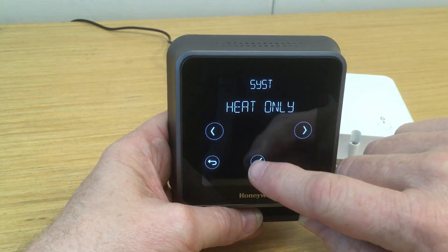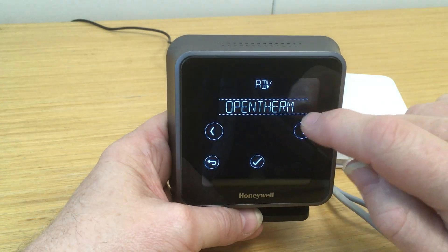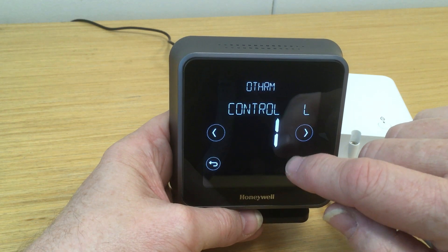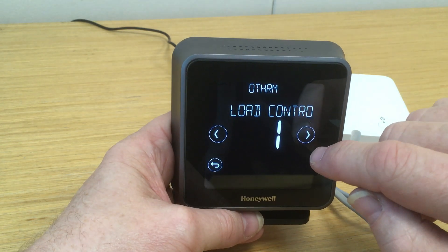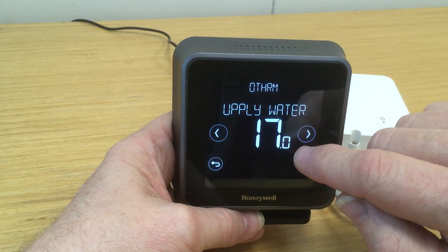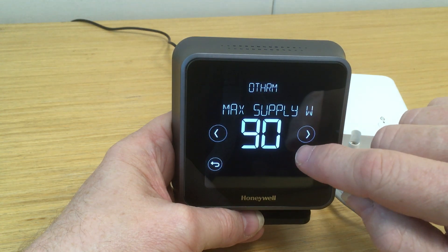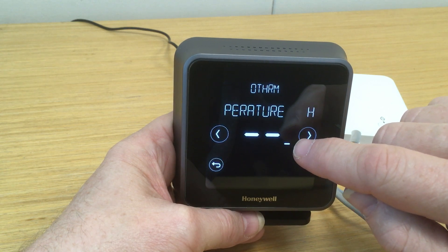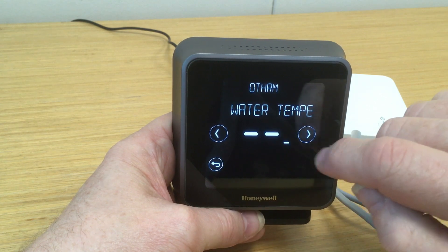If we now scroll forward to the next option, which is the OpenTherm, here we can see various aspects of the OpenTherm control. First of all it shows us that low load control is enabled, which is generally recommended, so we'll leave that as it is. We have various other data readouts from the boiler itself — the flow and return temperatures for example. Here we would have the instantaneous temperature readout should hot water be drawn off at the time, but of course as it's not, there'll be no readout there.